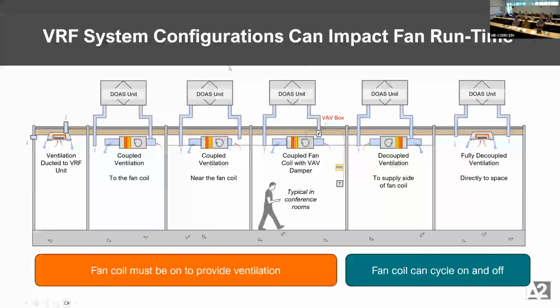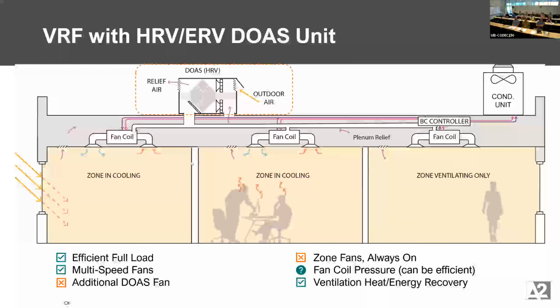I imagine in a high desert climate like Boise, you probably got a pretty decent difference in max capacity, design capacity, depending on whether you had the DOAS unit serving the ventilation load or the VRF system when you're piping it in. And with so many thousands of hours in that 25% to 75% range, that could have a really big impact on the efficiency of the compressor if you're oversizing and effectively sitting at that 11 IER and cycling so often, if you're oversizing so much to fully meet the ventilation load with the VRF.